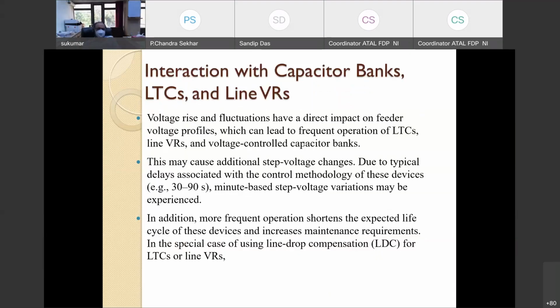Similarly, the tap changing transformers and the line voltage regulators can be placed in the distribution system for the proper operation of the capacitor bank and LTC. And the step voltage change can be handled by the proper operation of the tap changing transformer, because these tap changing transformers are generally mechanical and not very smooth in their operation.